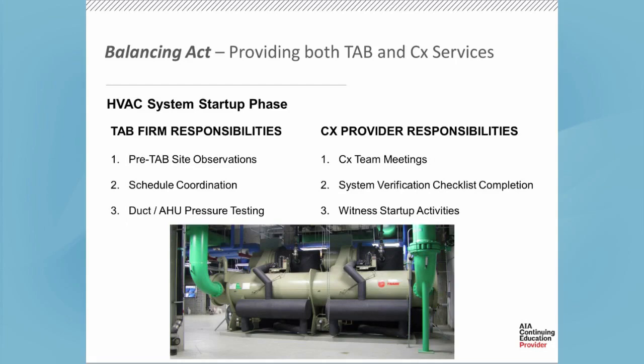So with respect to the HVAC system startup phase, there are some unique responsibilities here, and you're going to start seeing where the TAB firm is going to have a little bit more involvement at this phase. They should be walking the site at this point. They may not have in their scope to witness startup. That's commonly, at least on the projects on which we work, typically in the commissioning provider's scope. But they may still have some input, and they need to be doing their pre-TAB site observations just to ensure that those testing locations are being installed appropriately, that they have what they need, that they have access to components and things like that, and really looking at things before they get covered by insulation or ceilings and so forth. We really like to have an early walk there before the piping and the ductwork is wrapped in insulation, and let our TAB teams look and make sure that they have everything that they need and they're not going to foresee any problems.